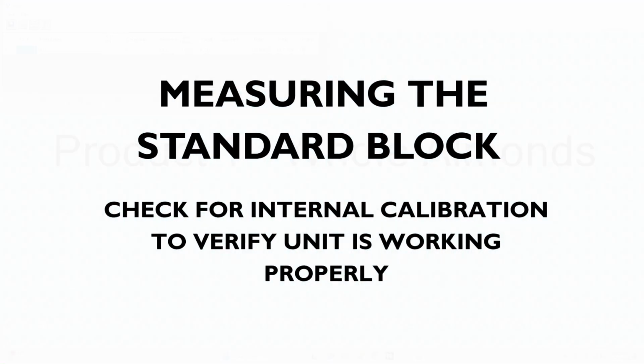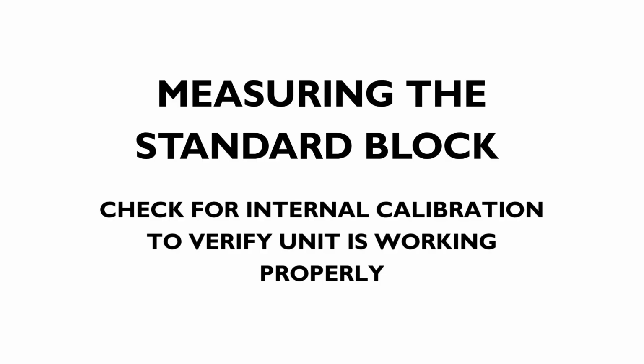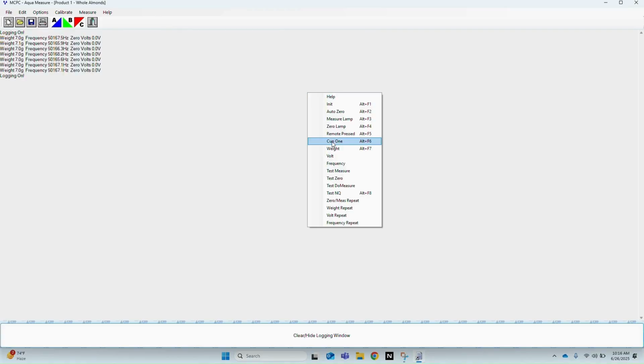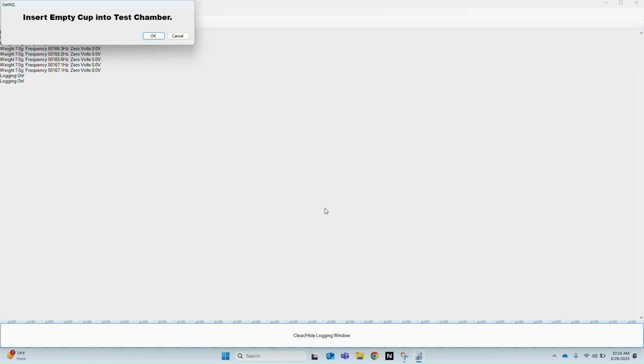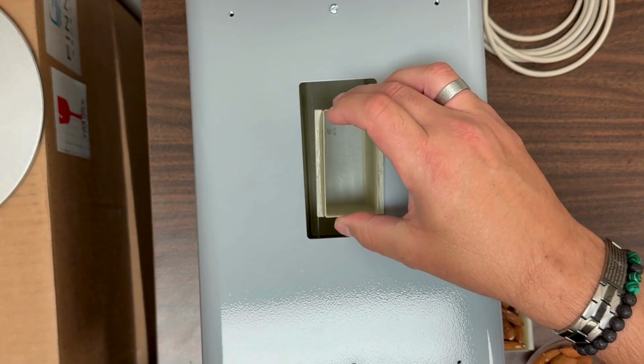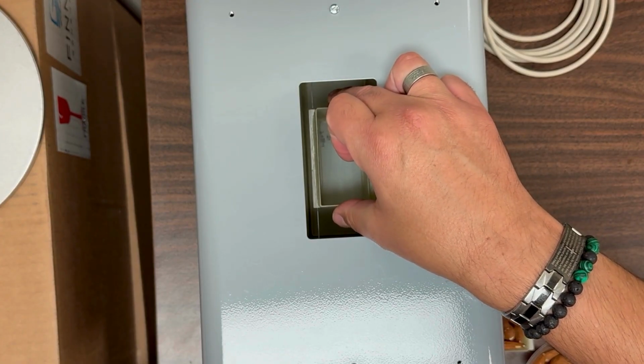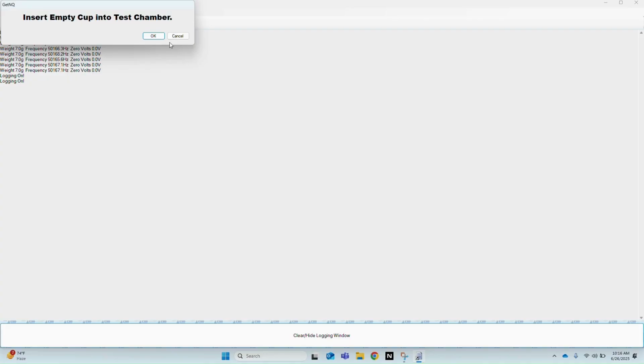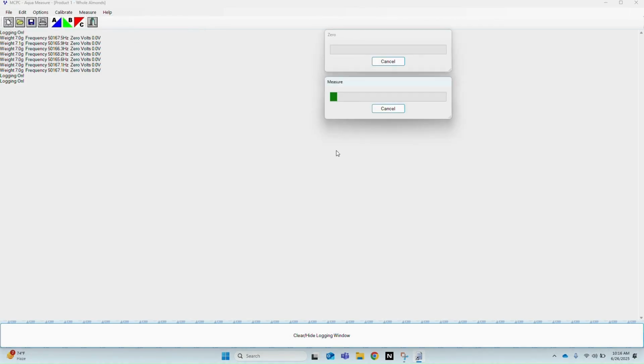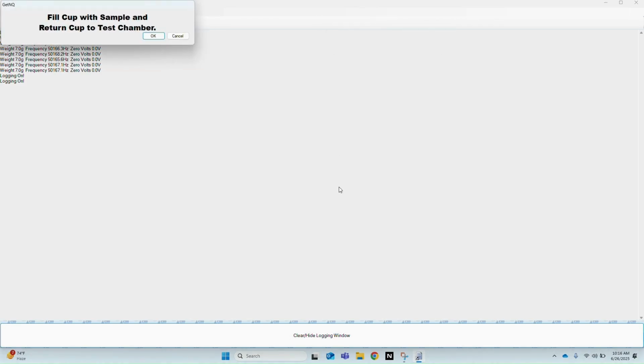The sample cup also has a purpose of measuring the standard block, which is used here to check for internal calibrations to make sure that your unit is working properly. So you follow the instructions by doing a test NQ test here, and it asks you to put in a sample, and then if you're running a test NQ, your sample would be your standard block, and each standard block is stamped with the serial number of the unit, the weight of the block, and the frequency of the block.